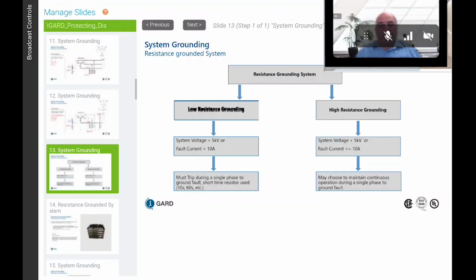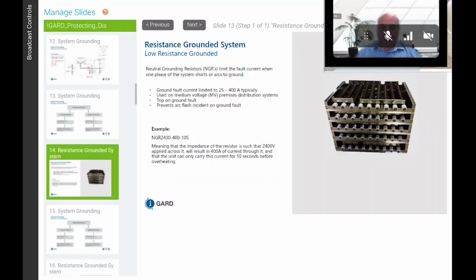But there's nothing really to stop you from using a high resistance grounded system where your voltage is higher than 5 kV, as long as you trip sequentially down to a safe condition again. So there's segregation. You can trip the faulted circuit, keeping your critical processes running. So an example of a low resistance grounded system, this one is 2400 volts, so it's meant for a 5 kV system.